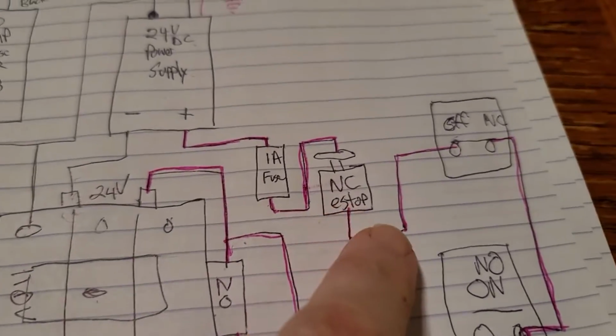So it comes out of that normally closed E-stop, and it's going to go over here through the off button. And the off button, make sure you see this, is normally closed. That's NC. And that's what this symbol is: two circles with the line touching it.